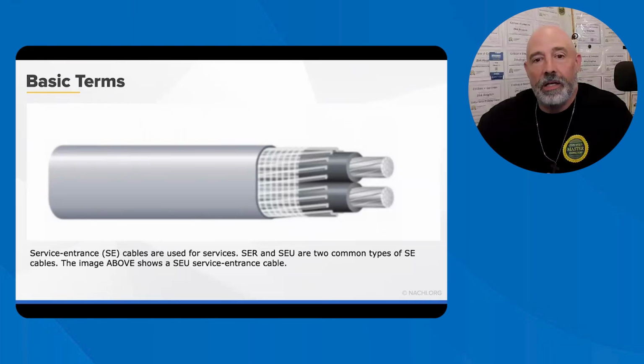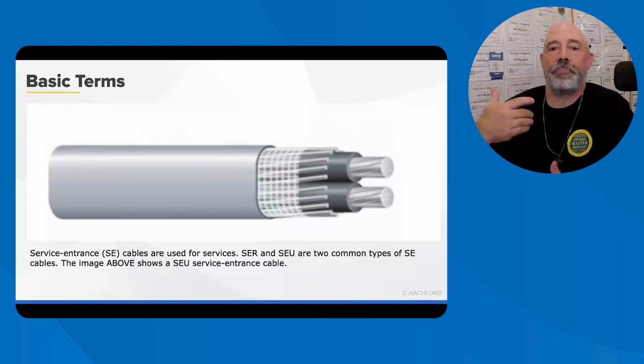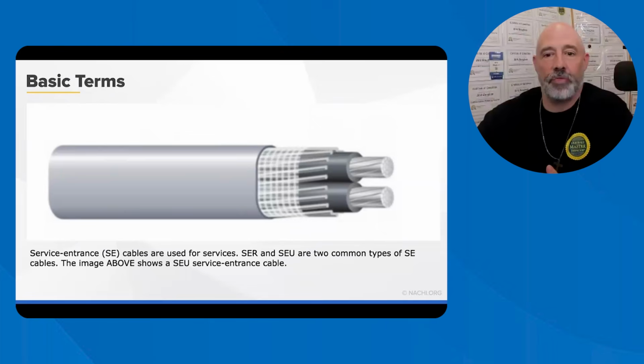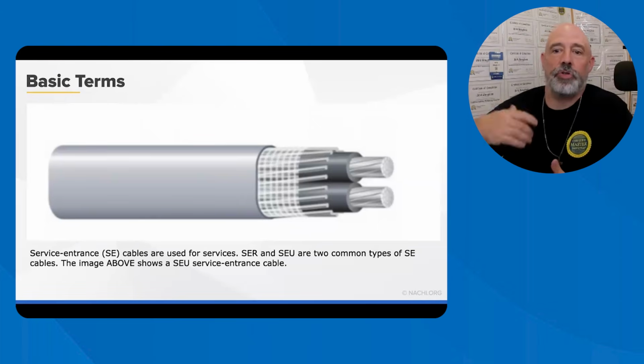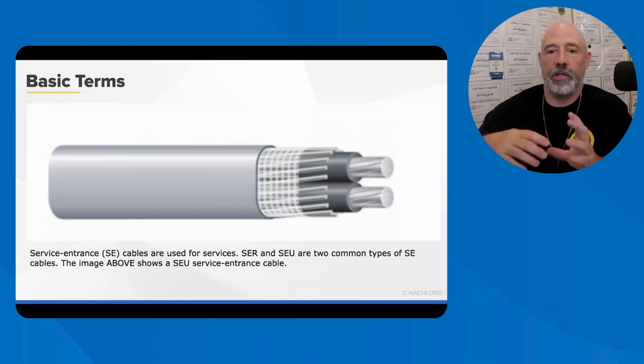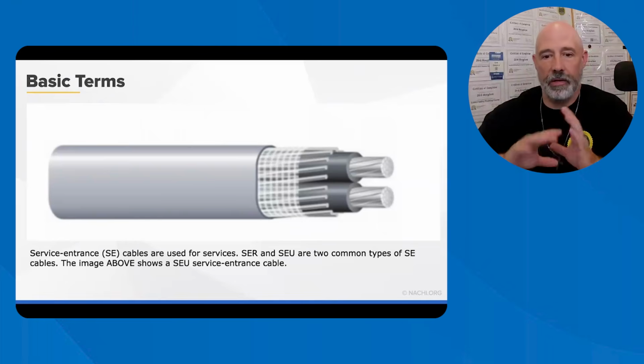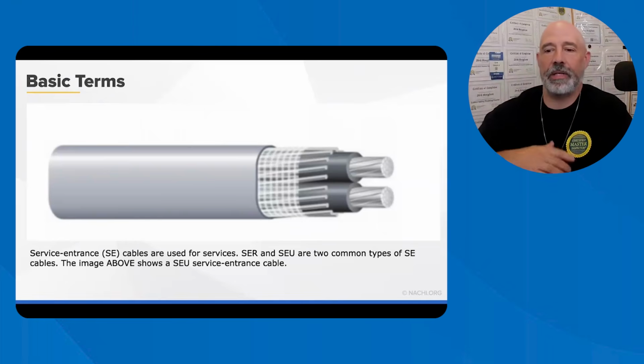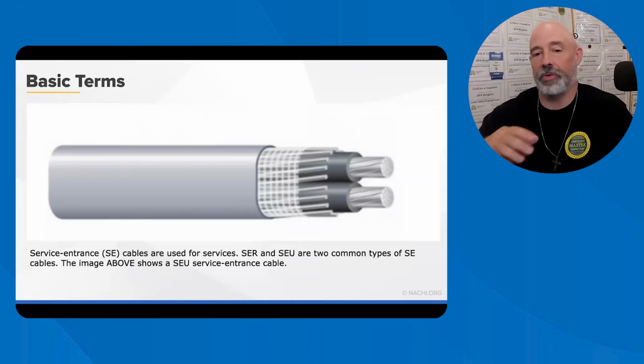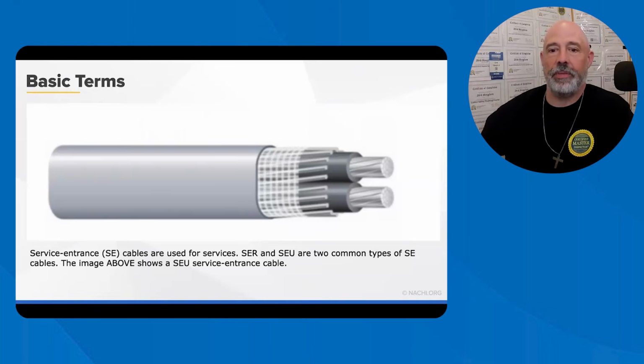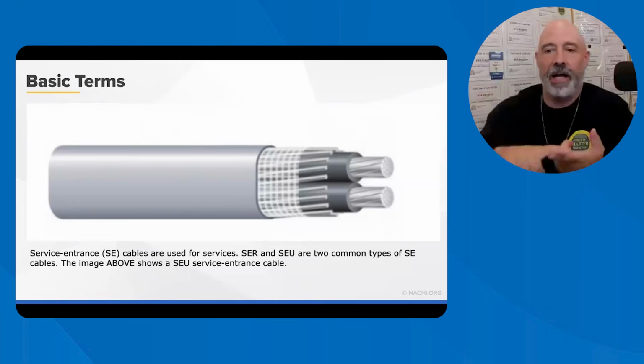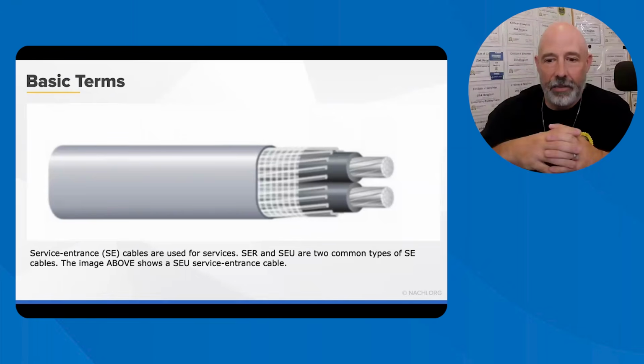Service: the conductors and equipment that either go underneath the ground or go over the top. That is your service. So SE and SEU wires: SE is your service entrance, and SEU is typically oval shaped with two conductors and a neutral conductor, used only up to the main service disconnect because it does not contain a separate ground conductor. SER cable, typically round, contains a hot, a neutral, and grounding conductors, making it suitable for feeders and subpanels after the main disconnect.